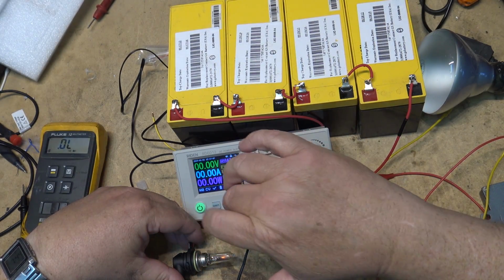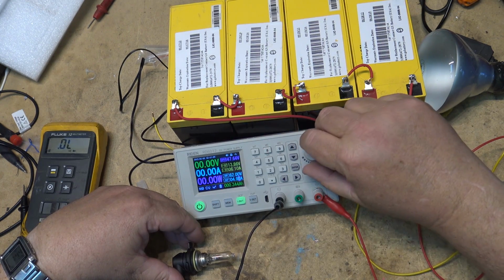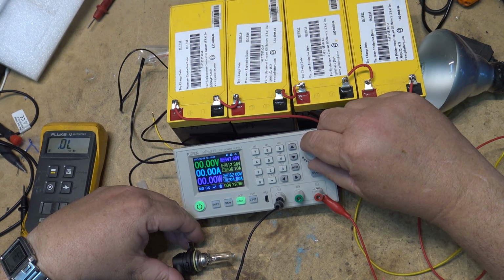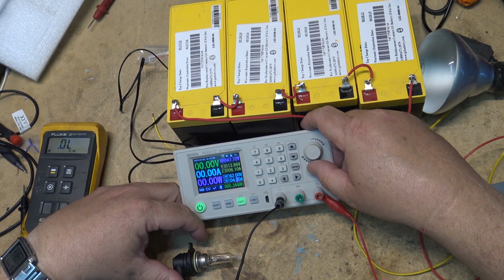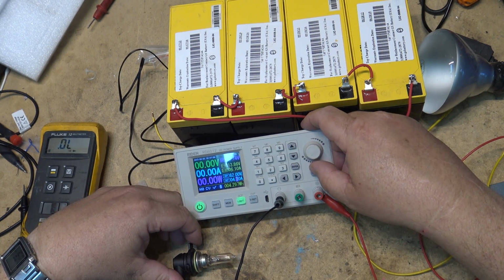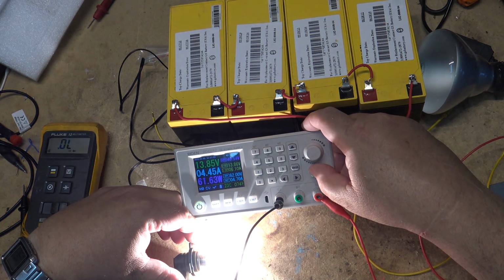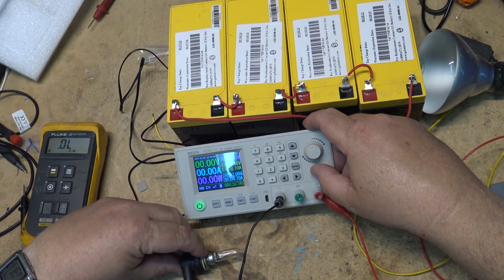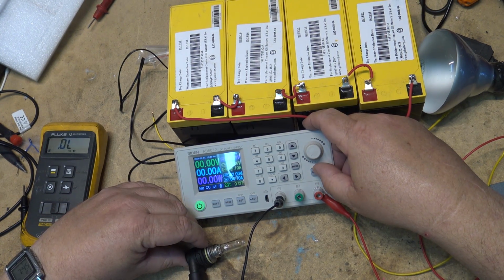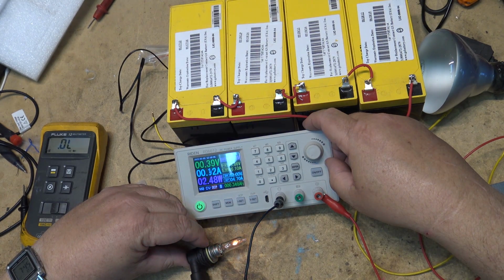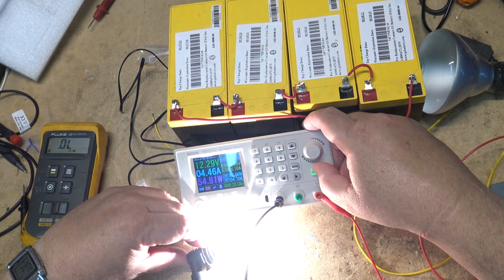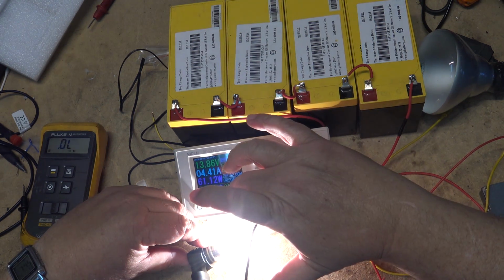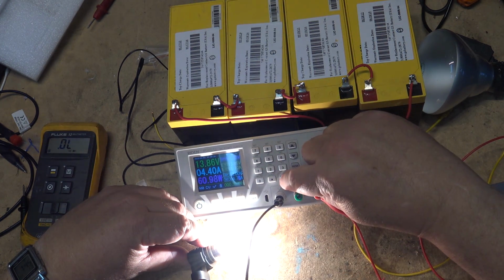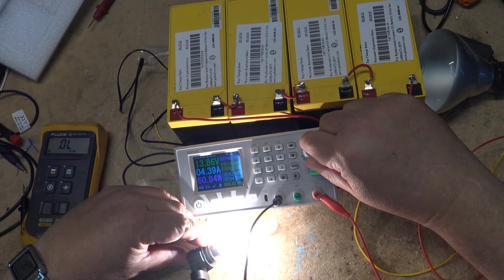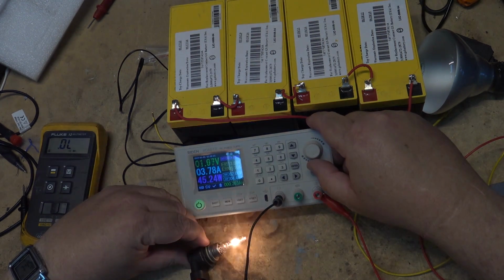Now I know it draws 4.5, so if I take the limit and make it 4.7, it's not going to start, it's going to shut off. But if I turn it on enough to keep the filament hot, it probably will allow me to go. There you go. Because when a filament is cold, it draws more current. So to start this thing up, it takes more than 4.7 amps initially, and it shuts down. If I keep it running, it'll run. In fact, I could set this probably to 4.4, and it will continue to run until I shut it off.